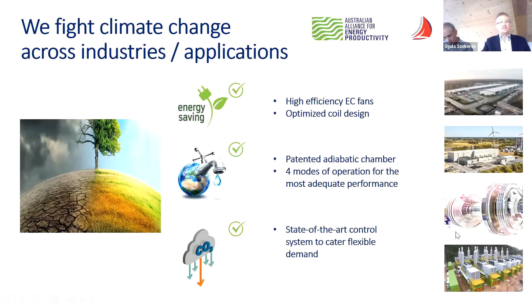Let's talk about adiabatic cooling and how it works. Basically we're speaking about a dry cooler solution, the core of the machine, to which we've added a technology called the adiabatic chamber. This means we're able to keep the cooling capacity, or the leaving water temperature out of the machine, constant, thanks to the fact that we can keep the ambient or incoming air temperature at a constant level.